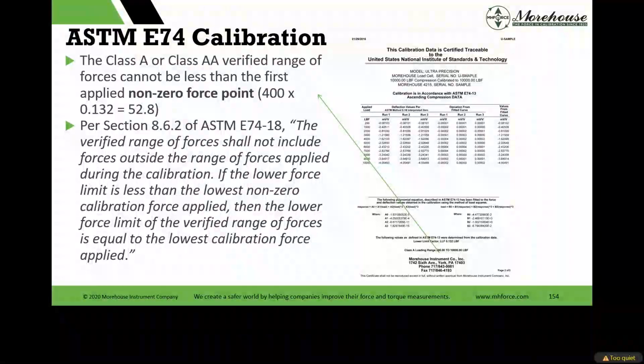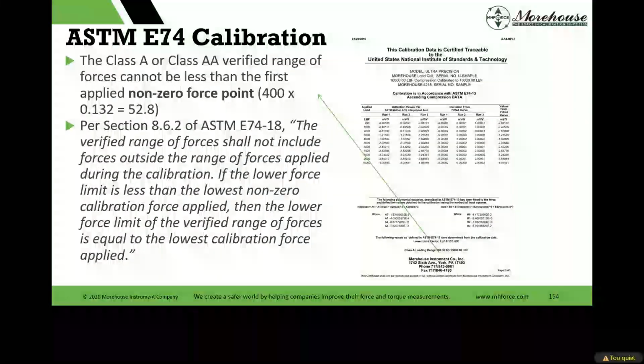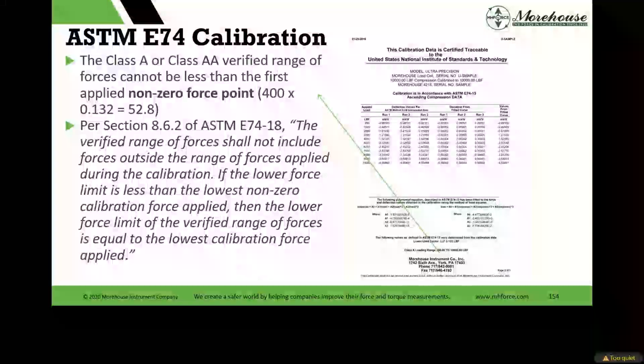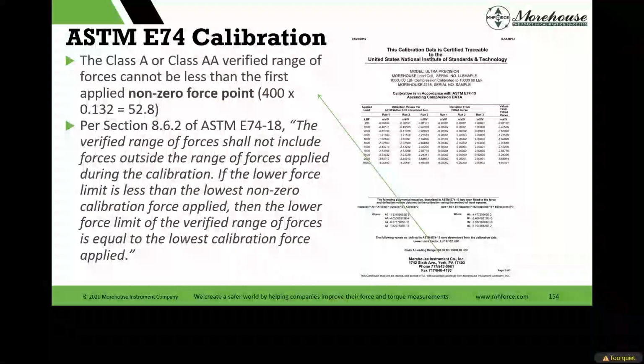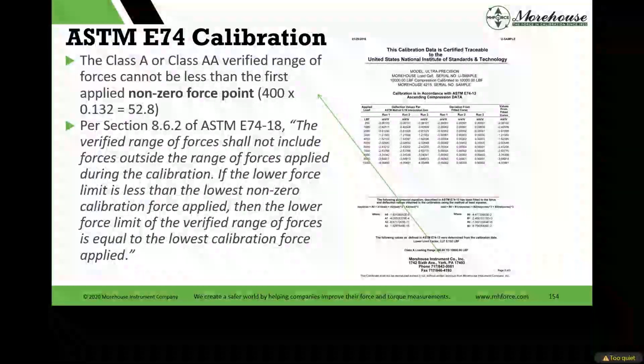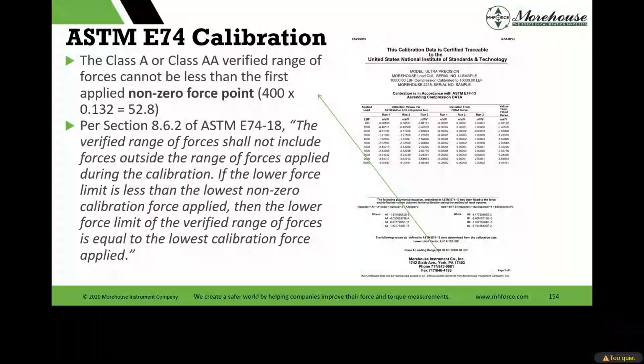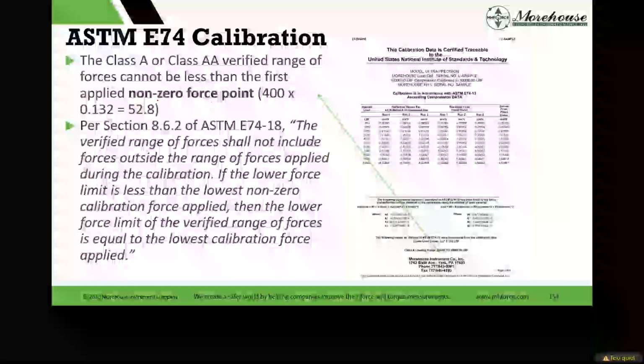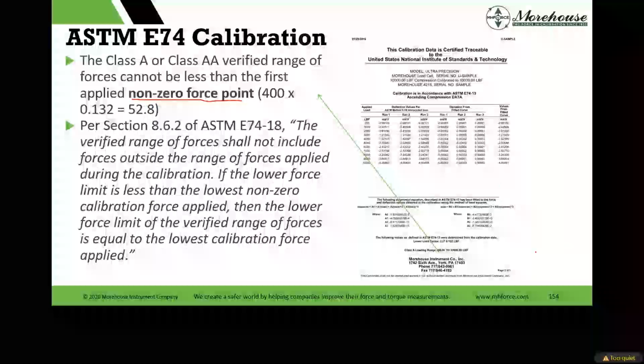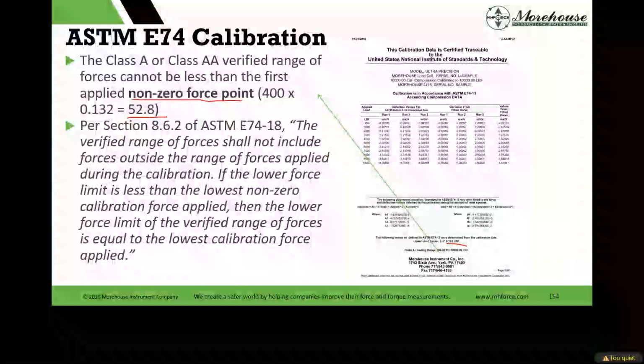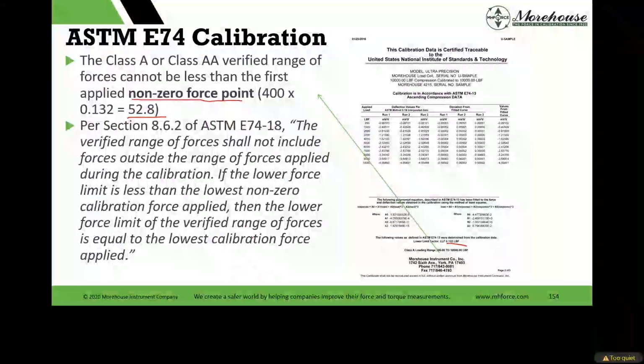The question earlier, if you have the 10,000 pound load cell, you could get ascending, descending points at 10,000 and 5,000, and have two different sheets and four different curves total, two for ascending, two for descending. Some additional stuff with the standard, it basically says non-zero force point. If we took this number here and multiplied that by 400, we get the first point as 52.8, but the standard says since you just did 200, you can't go that low.